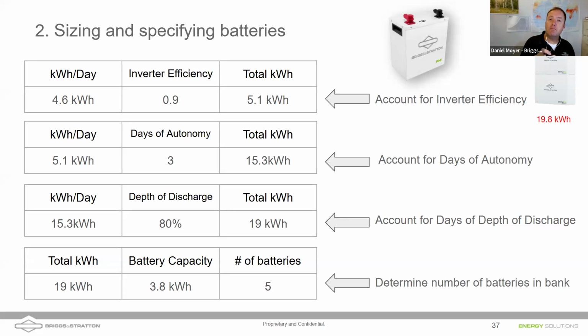All batteries, you don't want to discharge 100%, although on our new SimpliPHI 6.6 stacking battery, we do warranty to 100% depth of discharge. Unlimited cycles, no throughput warranty for 10 years. Great, one of the best warranties in the industry, but I would still recommend an 80% depth of discharge, so you still got a little reserve capacity in there.